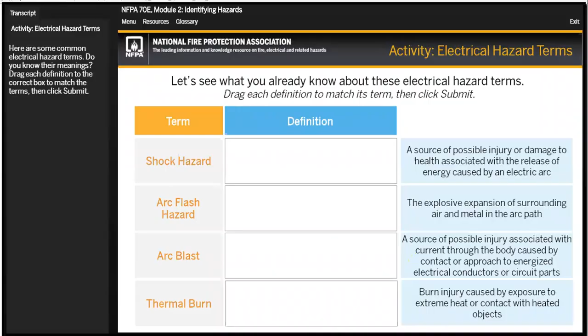Following that, in an arc flash event, there is an arc blast that occurs simultaneously, which causes the air to expand with pressure and melt the metals in its way, like conductors and enclosures. These become small molten dots, like bullets, red hot bullets, and their speed can go up to 700 miles per hour, a supersonic speed, which can penetrate the body and cause deep burns.